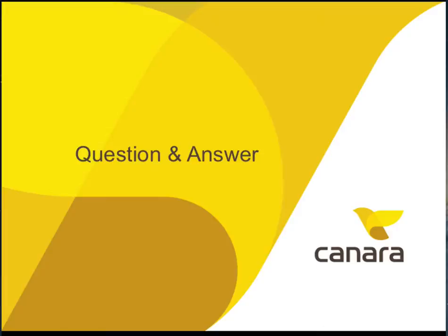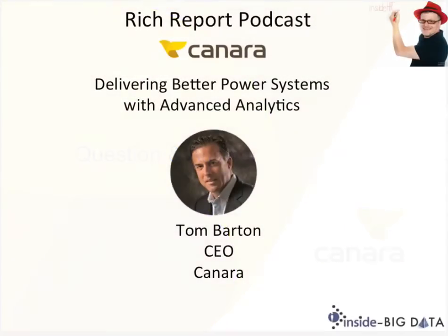That's a very good question. As a matter of fact, one of our largest battery vendor partners actually pays us to get sanitized access to our data, because they don't necessarily see all that stuff. Obviously any battery vendor can see their warranty claims, but they don't necessarily see all the data on a day-to-day basis as to exactly what happened with that battery. For our database, four times a day we're taking an impedance measurement, a voltage measurement, a temperature measurement at the negative battery post, which is the IEEE standard. We're looking at float voltages, we're looking at all kinds of things, and typically a battery vendor doesn't have access to that. The smarter, industry-leading battery vendors actually do want to see that data, because they want to correlate it with their warranty claims and failure analysis and see how different batteries are performing. So the short answer is yes, battery vendors are very interested in that data.